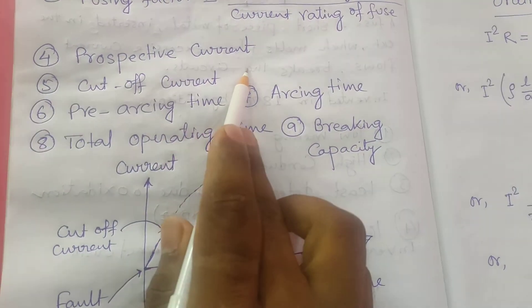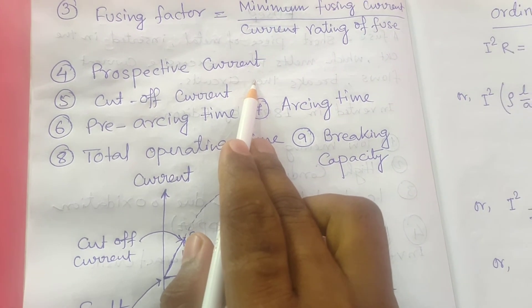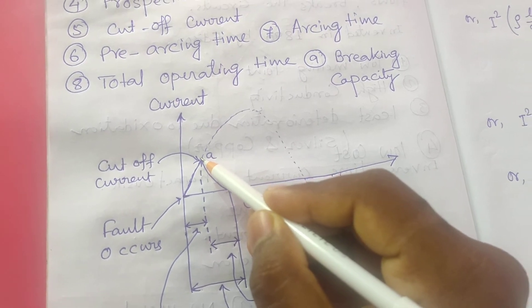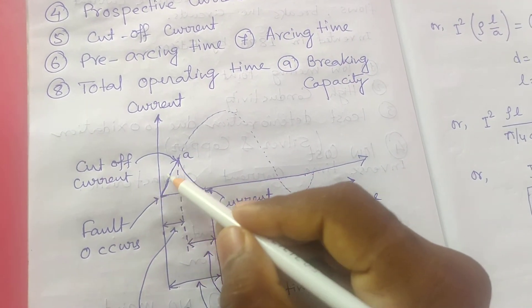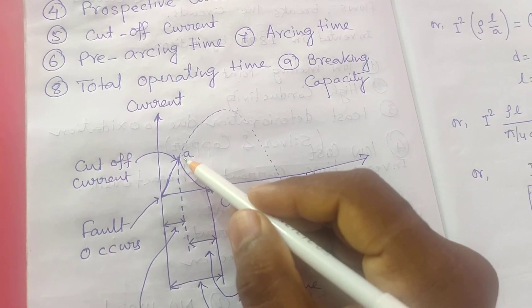What is the prospective current? Prospective current is an RMS value of the first loop of the fault current. It is the RMS value of the first loop of the fault current obtained if the fuse is replaced by an ordinary conductor of negligible resistance.